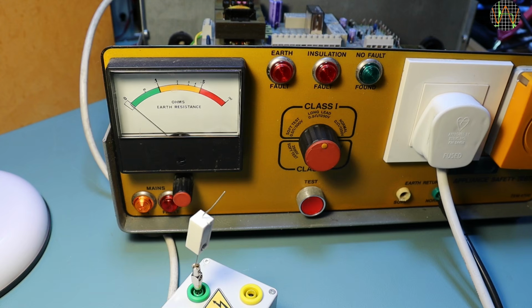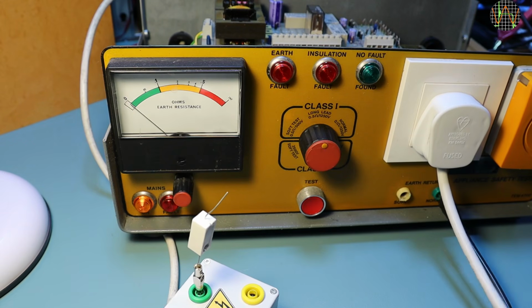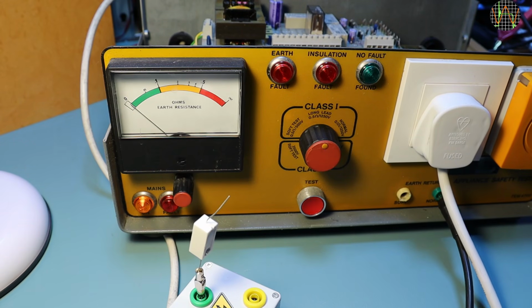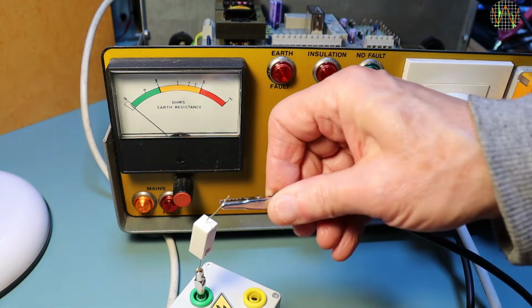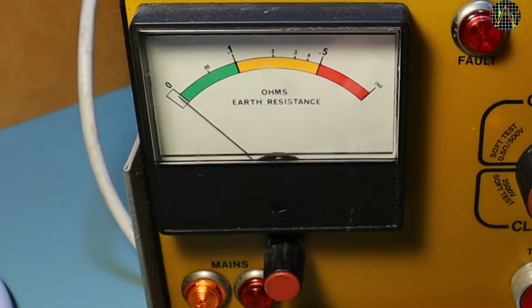Since there are trim ports for the earth resistance measurements, I want to check and fix the calibration of the class 1 normal setting. It should not show fault when the resistance is in the green area, that is below 0.1 ohm. For that, I thought I'd use a 0.1 ohm resistor as a reference, which you see here attached to the green terminal of my test rig.